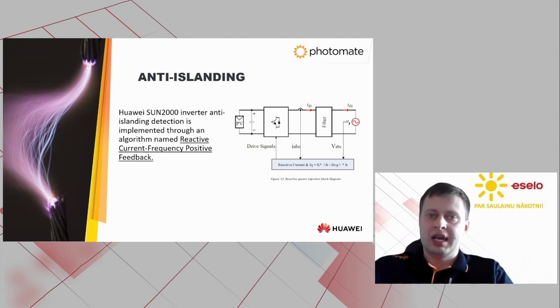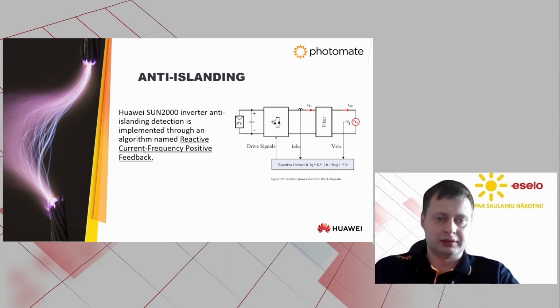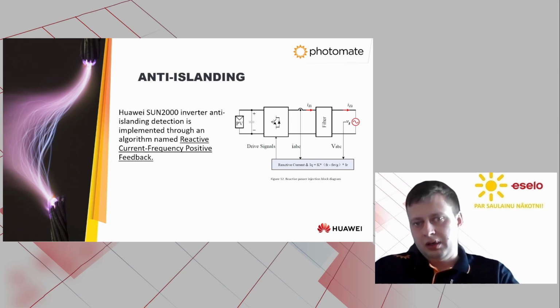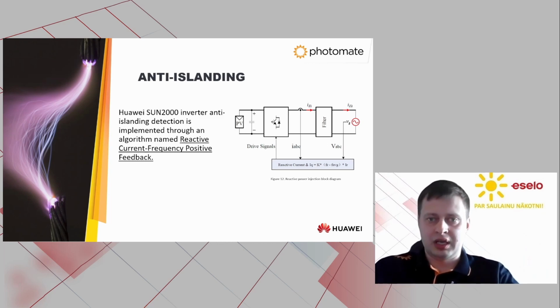A very common question is about anti-islanding. What happens if the grid is lost? For this purpose, the Huawei Sun 2000 inverters implement the algorithm known as reactive current frequency positive feedback. In very short, every time the inverter feeds some reactive current to the grid and checks if the grid gets affected by this current. Normally, the grid is very strong with very low resistance and is not affected by the small current. But if the grid is disconnected, all this current makes some changes. And if those changes are not within limits, the inverter is disconnected because it means it is working in island mode.